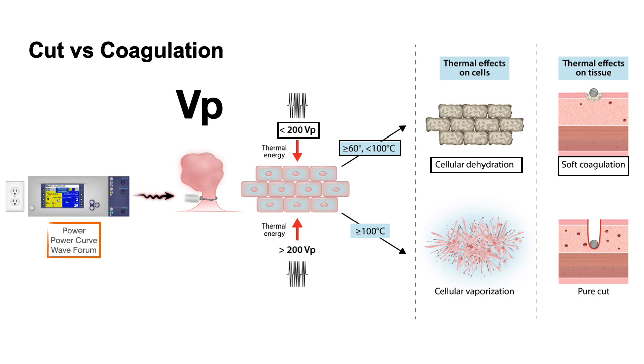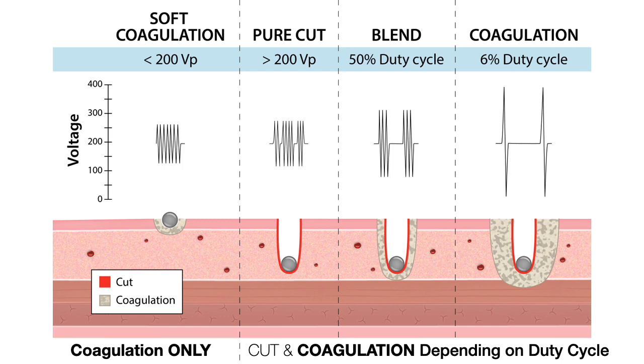In contrast to below 200 peak volts, if you increase it to above that, it results in rapid heat generation to the point of boiling, that results in cellular vaporization and disruption of the cellular membranes very quickly, and eventually a pure cut results. So these are the two basic principles for cut and coagulation: rapid generation of heat or a slow simmering heat, cellular vaporization or cellular dehydration. So let us look at it in a different way.